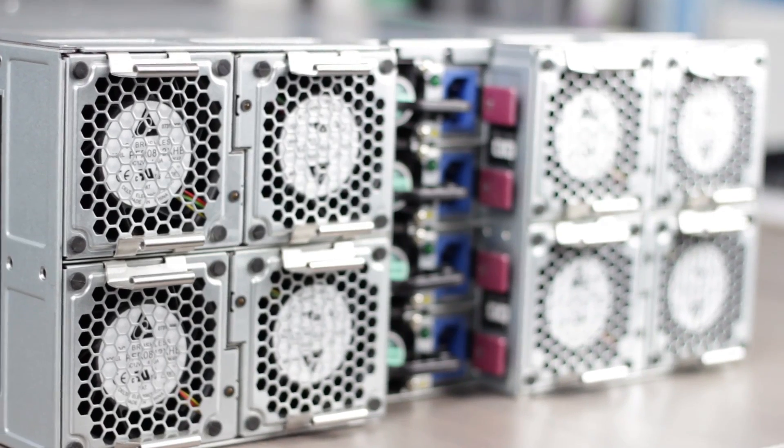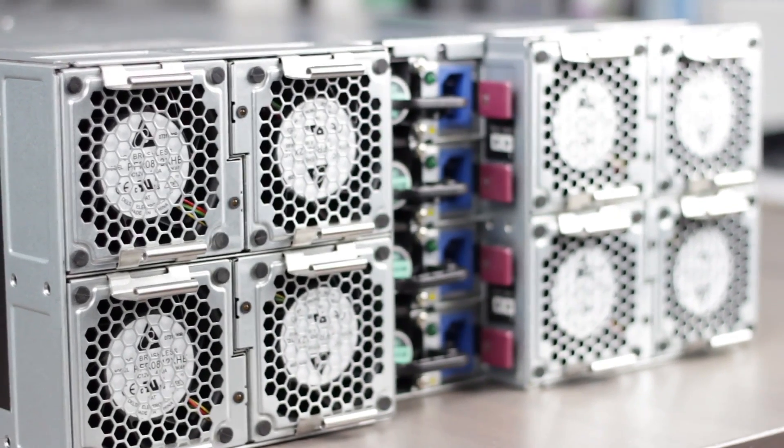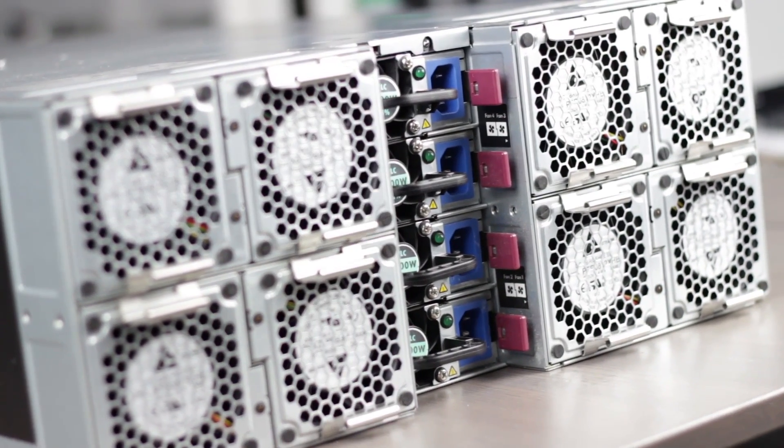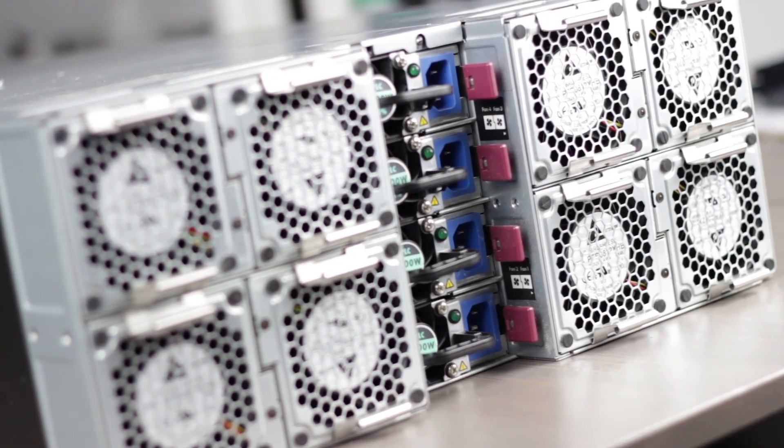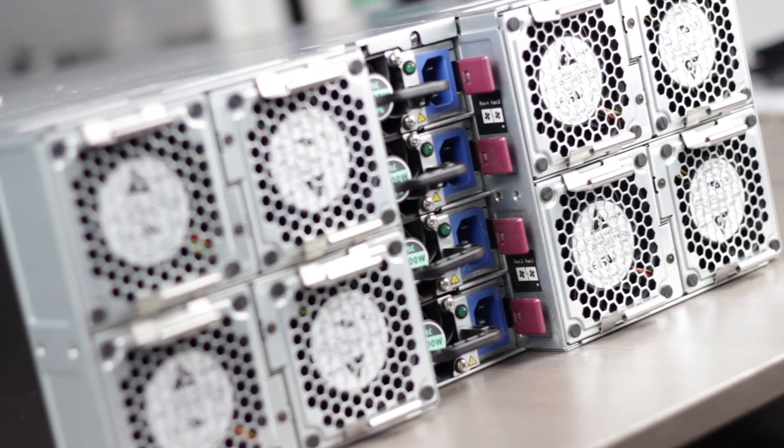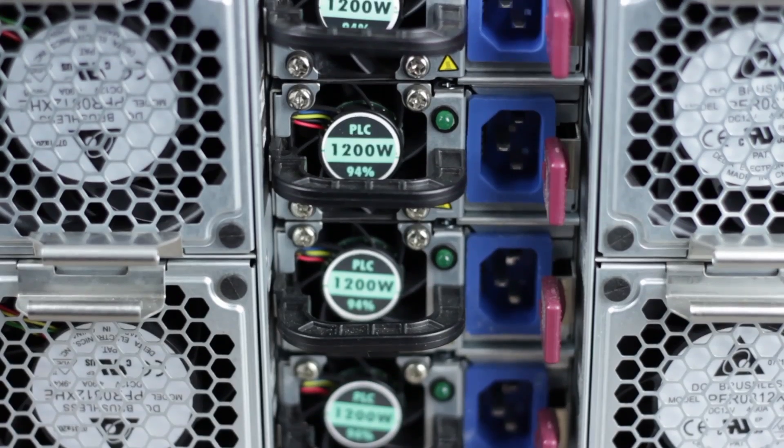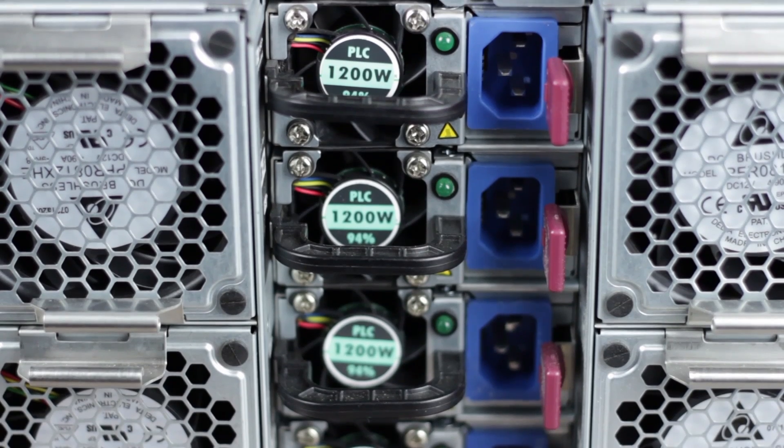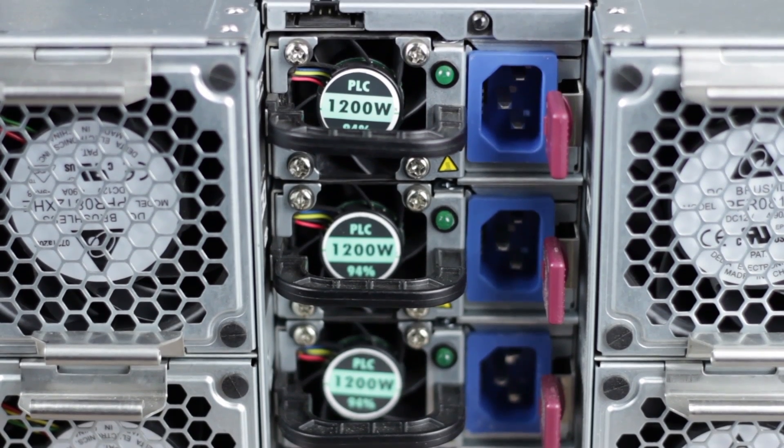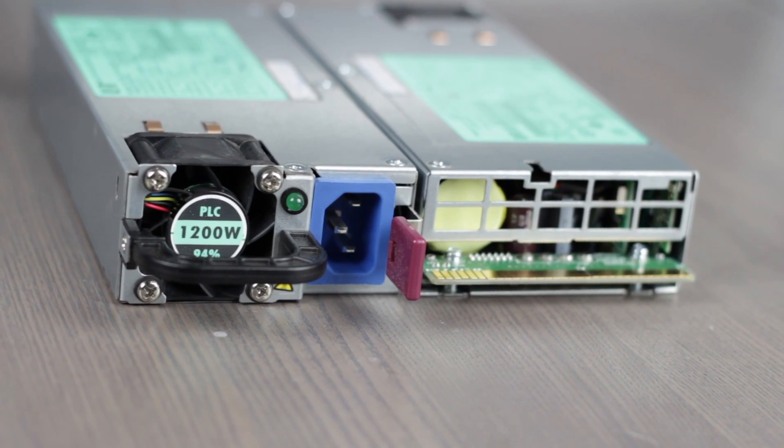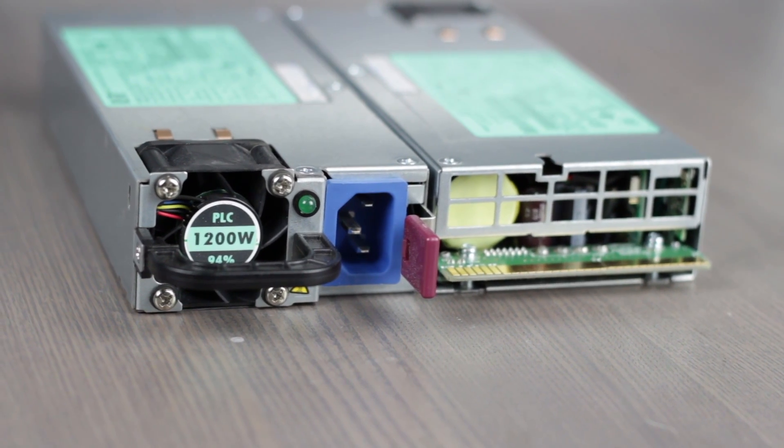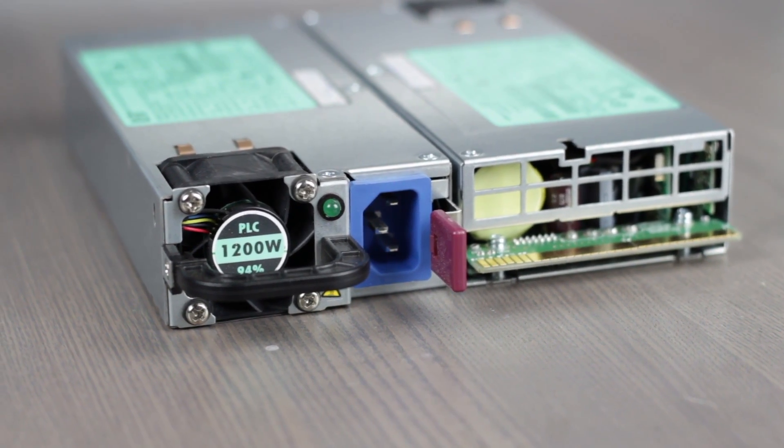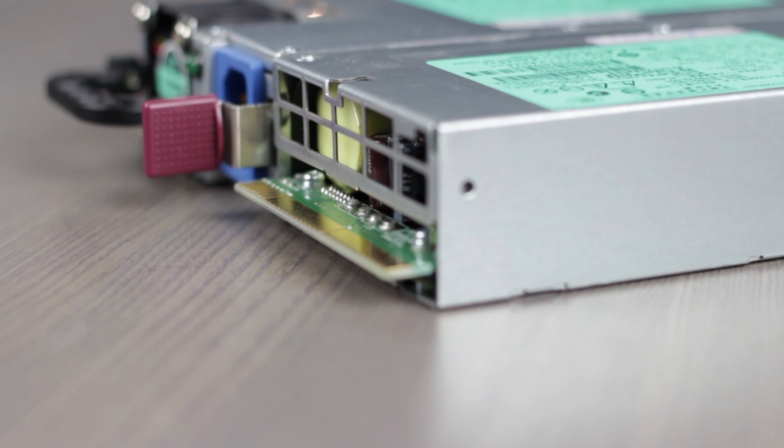On the back of the server, we can see eight non-redundant fans and slots for four hot-plug power supplies. We have four 1,200-watt 94% efficiency power supplies that supply power to the entire chassis.